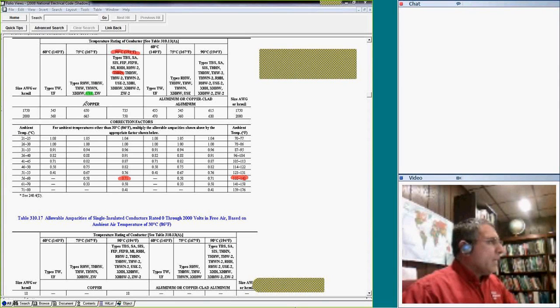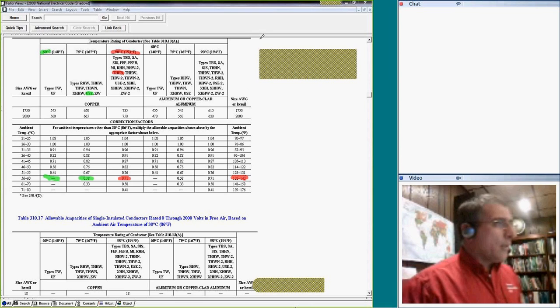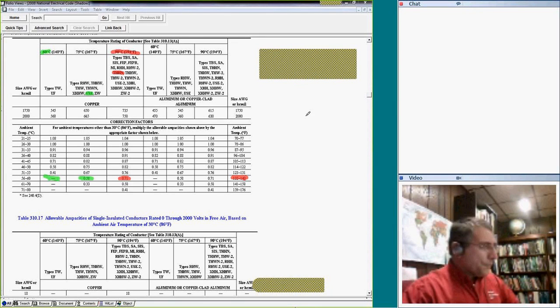Is there a problem with that? If you are to use a USE conductor, well, guess what? Now you are down to 0.58. If you look here, they don't want you to use even the 60-degree column. There is no number for it. There's nothing here for it. So that's how, if you use a USE conductor, your derating is 0.58, versus 0.71 if you use a THHN conductor, which we use all the time. THHN, THW.